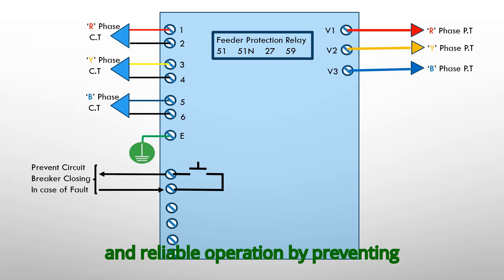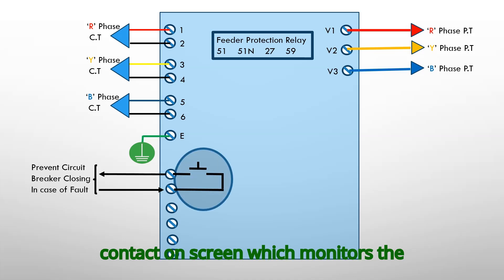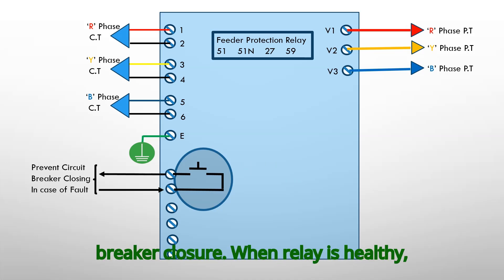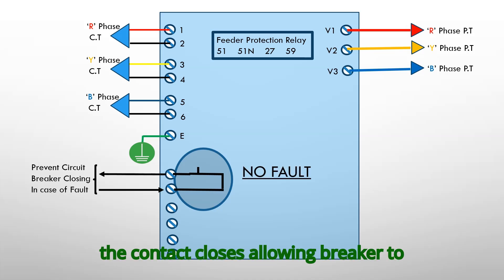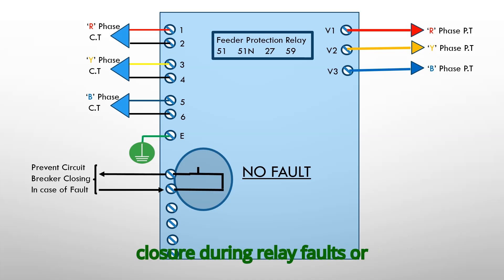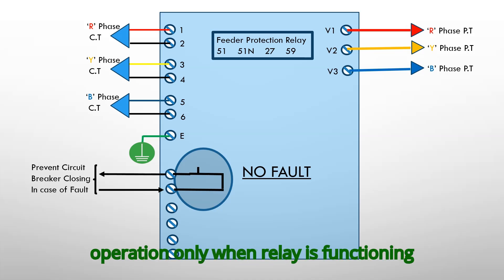Interlocks ensure safe and reliable operation by preventing unwanted breaker closures. Notice the contact on screen which monitors the relay health. When the relay is unhealthy, the contact opens, preventing breaker closure. When the relay is healthy, the contact closes, allowing the breaker to close if the close command is given. This interlock mechanism prevents breaker closure during relay faults or maintenance and ensures breaker operation only when the relay is functioning correctly.